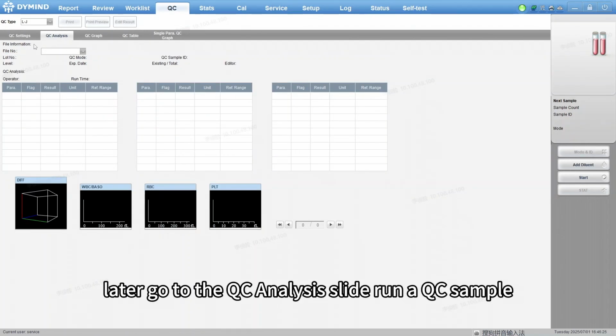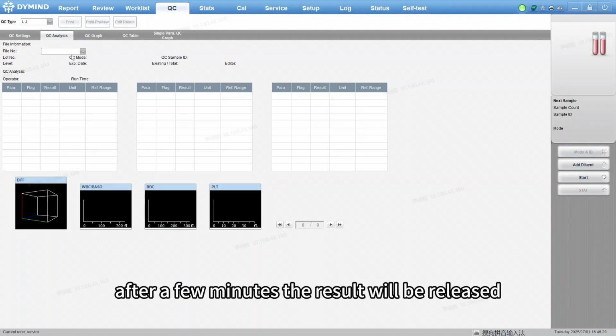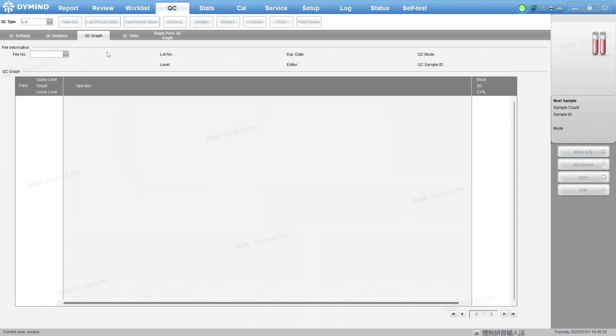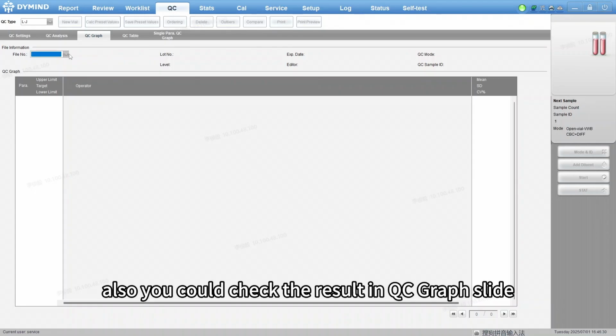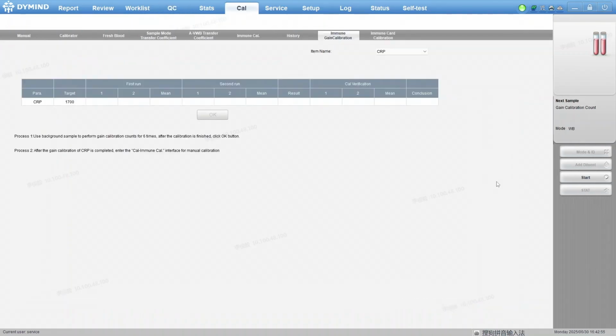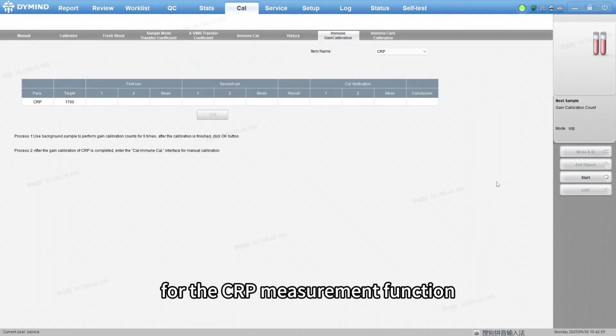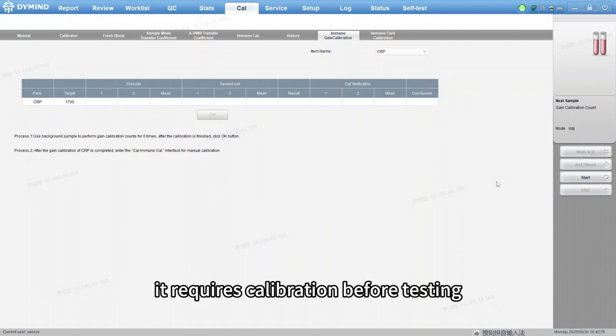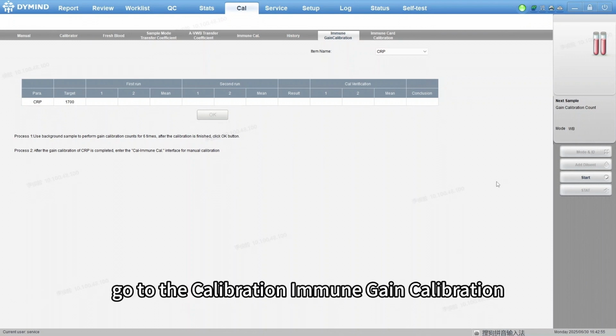Later, go to the QC analysis slide and run a QC sample. After a few minutes, the result will be released. Also, you can check the result in the QC graph slide. The CRP measurement function requires calibration before testing. Go to the calibration, immune gain calibration.